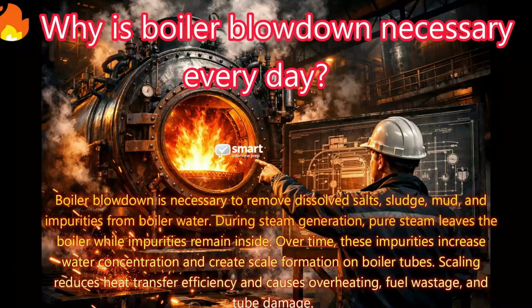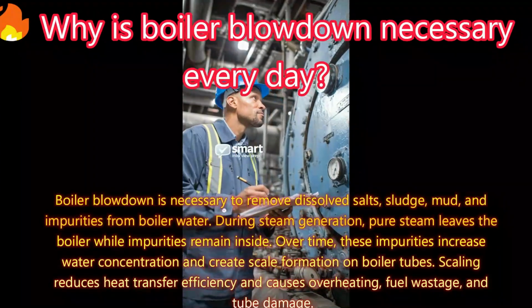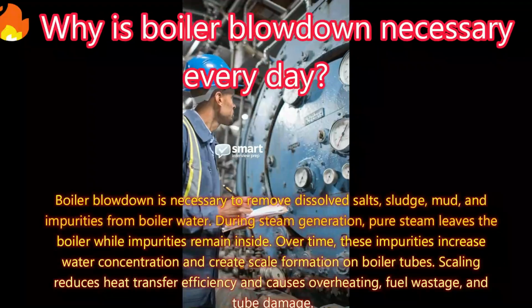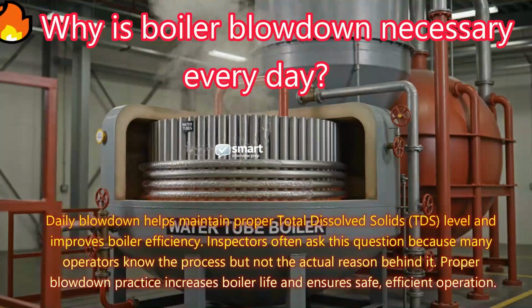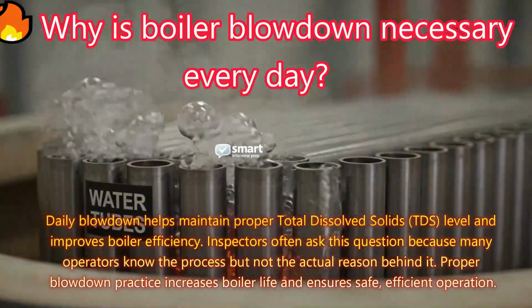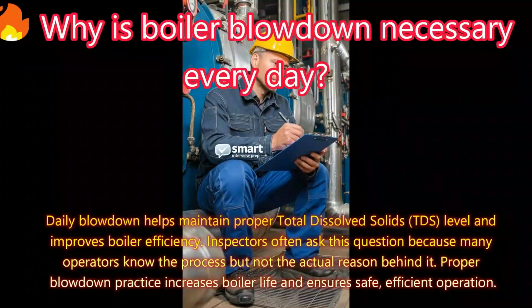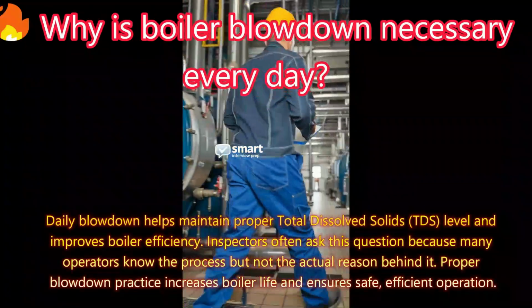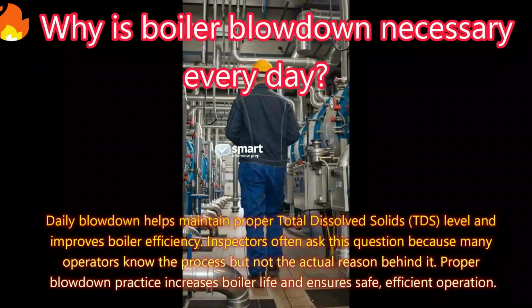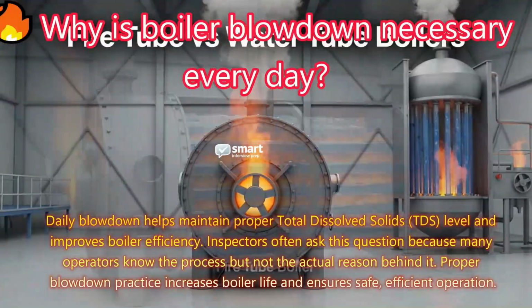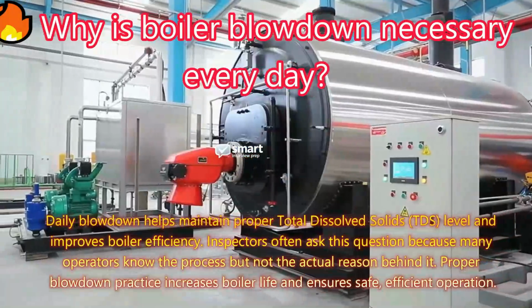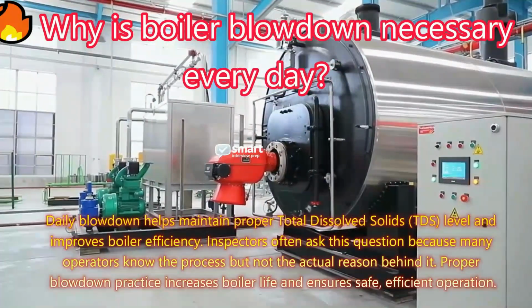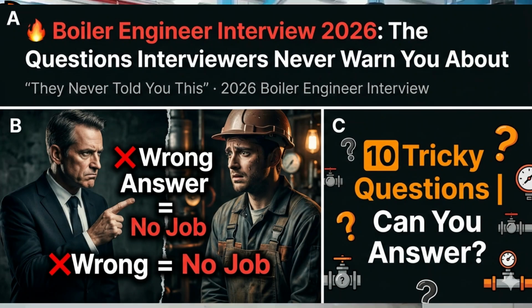Scaling reduces heat transfer efficiency and causes overheating, fuel wastage, and tube damage. Daily blowdown helps maintain proper total dissolved solids, TDS, level and improves boiler efficiency. Inspectors often ask this question because many operators know the process but not the actual reason behind it. Proper blowdown practice increases boiler life and ensures safe, efficient operation.